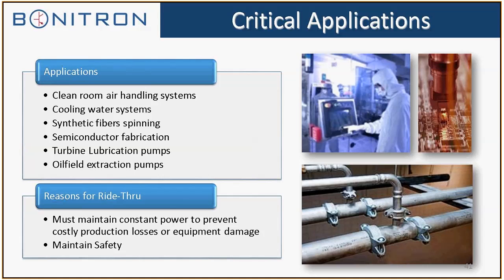Either you deal with the regen and restart the drive, which can take up to 8 hours to restart, because you have to let all the oil drain out into the line. You can't start it under full load like that. Or you ride through the event and put a safety brake on it, like a dynamic braking resistor, in case it doesn't ride through the event and it still has to deal with the regen. But the actual best solution for this is to just ride through the event, which usually are anywhere from 1 to 2 seconds. And then you don't have to restart it and you don't lose production.